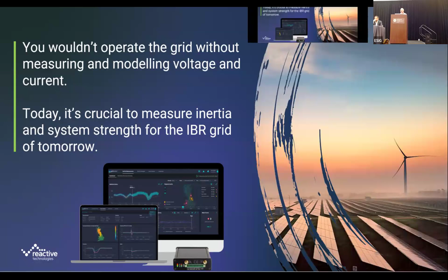So then very quickly, what are we doing? My fundamental message is that no one in this room would dream of operating a grid without measuring the voltage and current on that grid. So why would you try and operate that grid without measuring the inertia and system strength, because, as you've heard this morning, they become critical security parameters for that system.